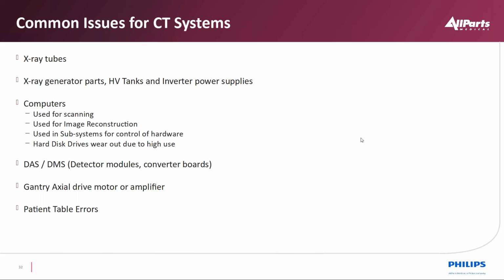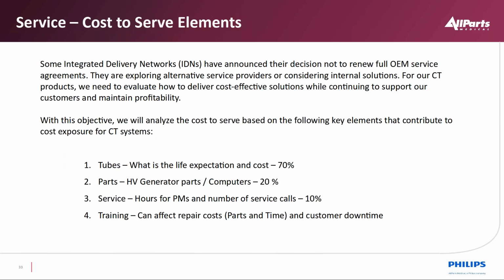Okay. Then we're rotating that gantry. Sometimes the gantry, the rotating part itself, is over 3,000 pounds. So we're accelerating it, we're changing its speed depending on the type of study, and then we're stopping it, okay? And then one of the least problems that we have, other than the covers maybe on tables because of gurney strikes, is table errors. Because typically when we do a scan, we just lift the table up to a given fixed location and then move it in and out.